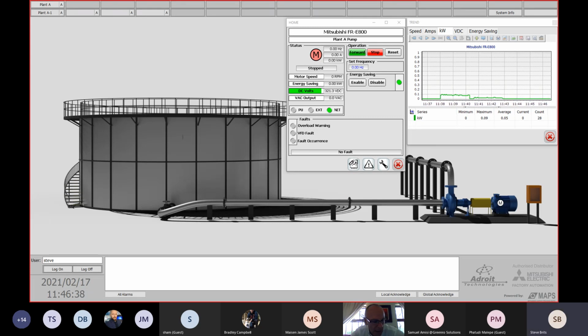Okay, how does the 5 Hz setting impact the long-term operation of the motor? Absolutely nothing. Your motor might even last longer. The only thing you need to always keep in mind is that you can run a factory motor at 25 Hz for the next 10 years. The motor won't burn out.